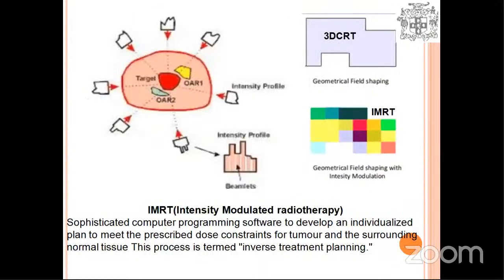A step ahead of 3D conformal is intensity modulated radiotherapy, where in addition to the benefits of 3D CRT, the individual beam coming out can be modulated. The entire beam is broken down into small beamlets. Imagine your computer screen made of pixels — if you are able to modify the intensity of each of these pixels or beamlets, you can get what we call a dose wash, like the same beam but with different intensities in different sections of the field that the area is exposed to.